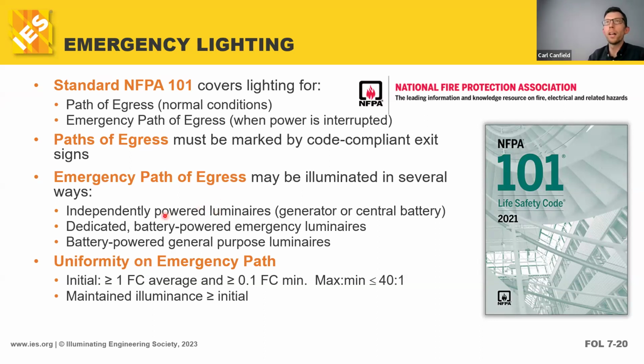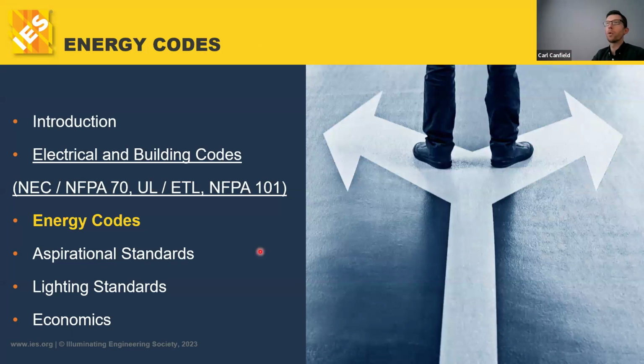There are a couple typical power sources for this emergency lighting, right? It can be on a generator, a diesel or natural gas powered generator. It can be with dedicated battery devices, either in the luminaire or the frog eyes or the bug eyes. Those little dedicated, kind of ugly industrial looking devices just sitting on the wall, they kind of look like frog eyes. There can also be an emergency inverter, which is a large centralized battery with inverter technology to allow the DC battery voltage to power AC lights. And all of these sources have to provide 90 minutes minimum of backup lighting to get folks out of the building. So 90 minutes, 1 foot candle along the path of egress, 0.1 minimum. These are some requirements of NFPA 101 life safety code. Very important stuff.